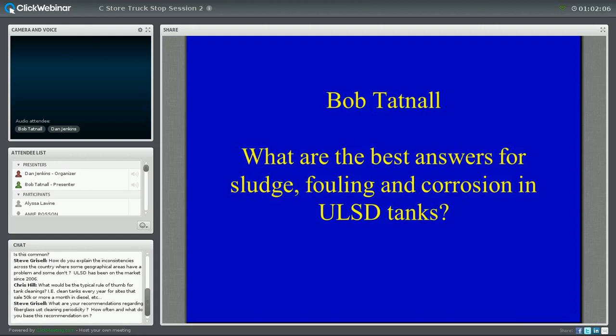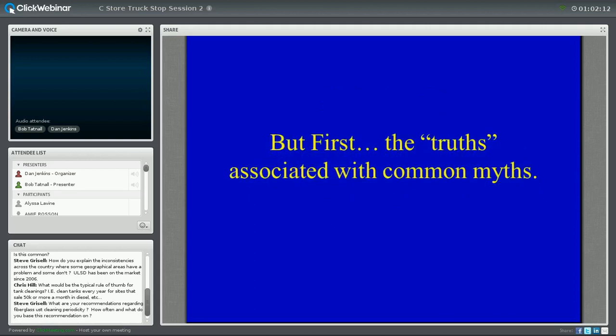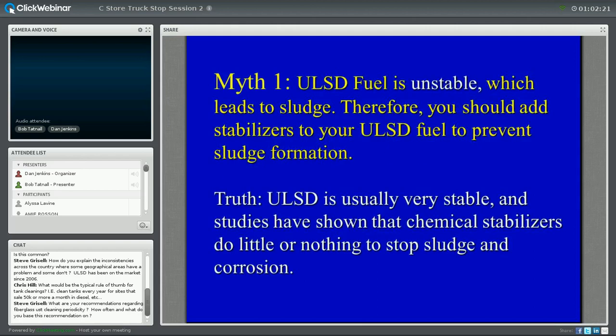Okay, I'm going to move along, and I hope I answered your questions adequately. If not, ask again. What do we do? First, I want to quickly nail those myths that Dan talked about, and some of them you've already heard the truth. I'll just remind you, the myth is that ultra-low sulfur diesel fuel is unstable. I've already told you, ultra-low sulfur diesel fuel is usually very stable. It's a beautifully stable material, and normally there is no reason you would need to add a stabilizer. There are certain special situations that can cause instability, and those we'll save for another day, but they don't involve sludge fouling and corrosion.